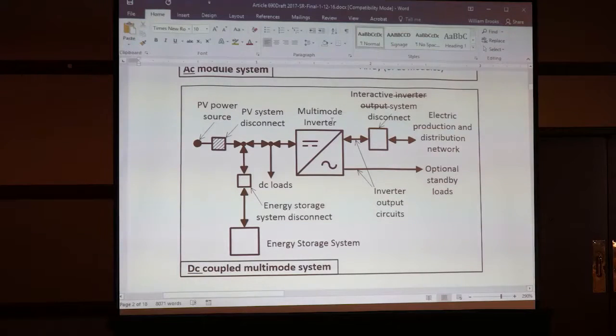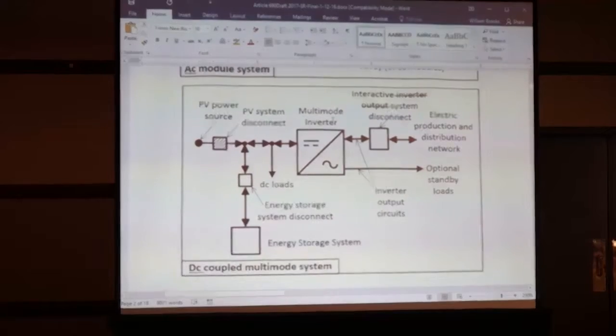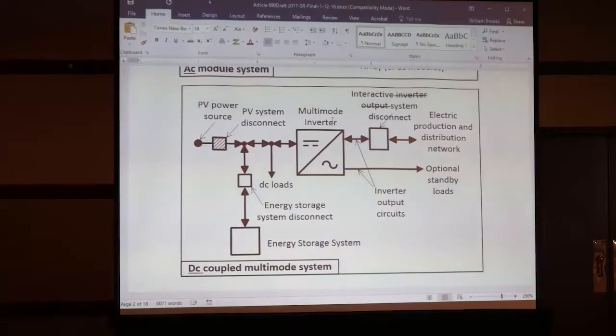Now let's talk about a DC coupled system. A DC coupled system can have any number of DC power sources, including the PV array. And of course, we have an energy storage system. That energy storage system has an energy storage system disconnecting means. Okay? The PV power source has a PV system disconnect. This is where the PV system stops. And this is a huge change from 2014 to 2017. All right, it's a very fundamental change.